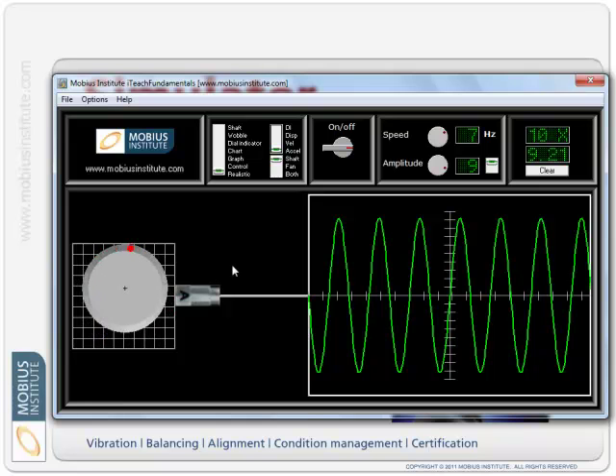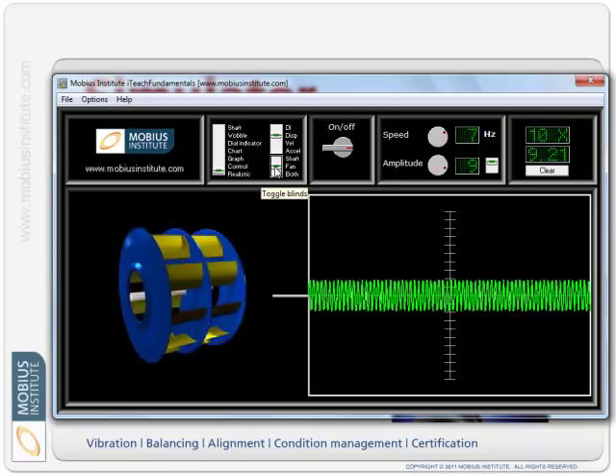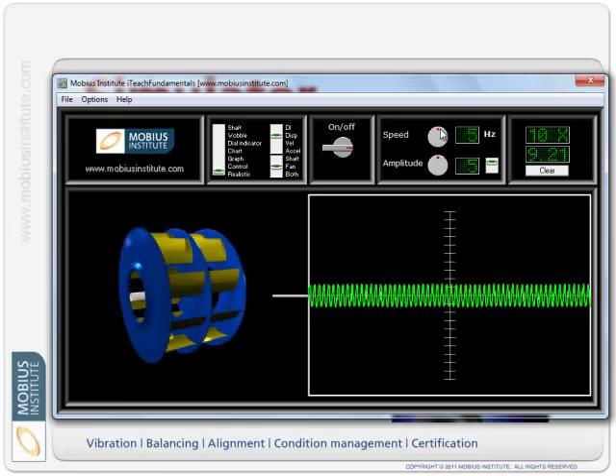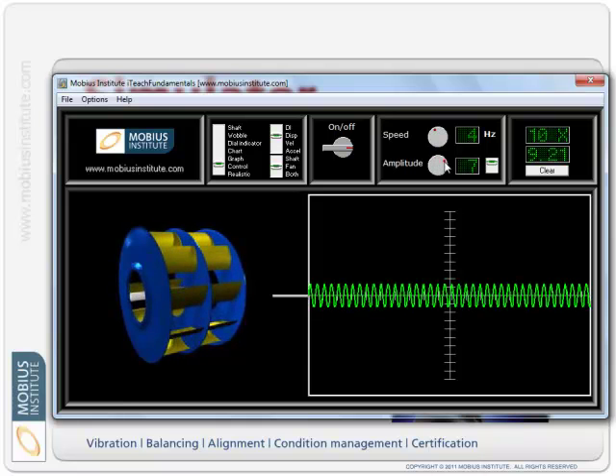Now another thing we can do is say, what if we were looking at not just the shaft movement, but the fan itself? Remember, this is the fan that we started with. I'll just back that off so it's a bit easier to see those waveforms. Now, instead of the vibration changing once per revolution, the fan has ten blades, so we get ten vibrations per revolution.